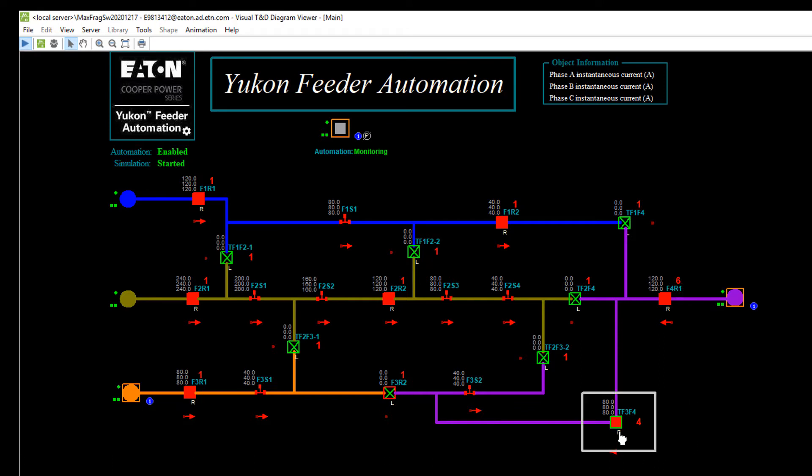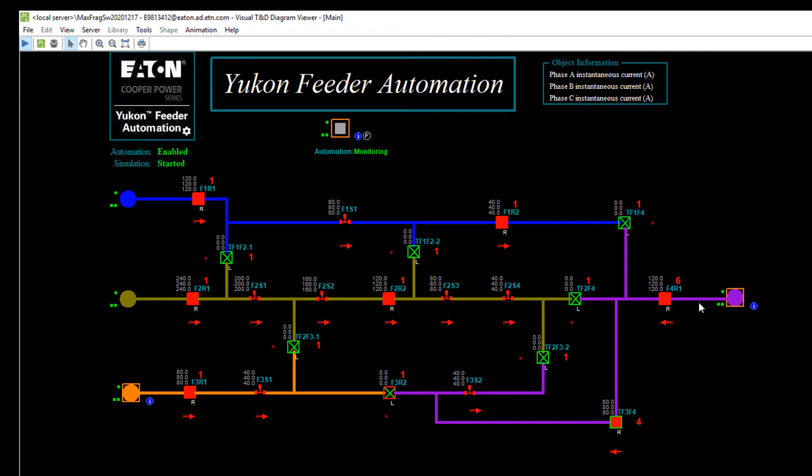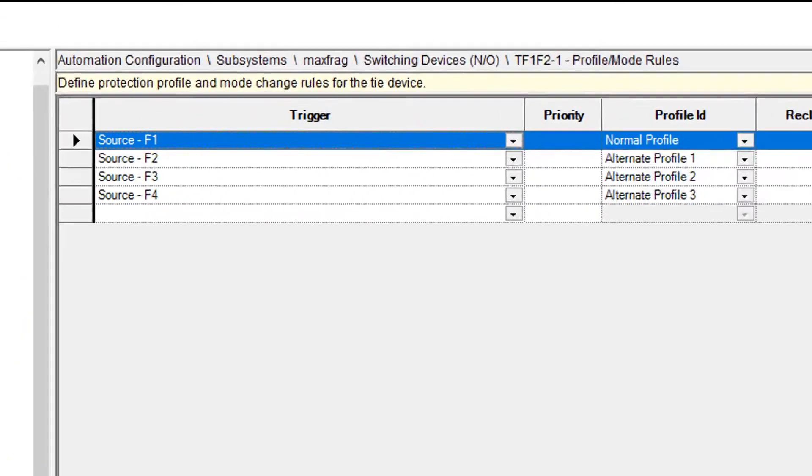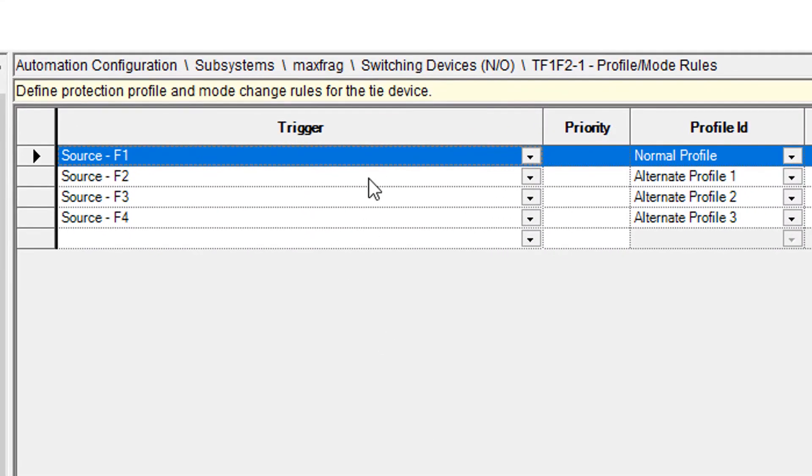Now you'll also notice that this device switched its profile over to a four. It did that because now this normally open point is fed off of feeder four. If I go back into my topology editor and look at the normally open point profiles and the profile mode rules, we can see.